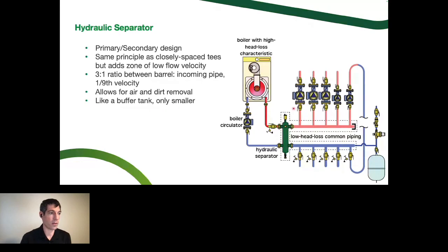We've tested this with some other devices on the market where we put a flow meter right here. You could even just look at the screens on the circulators in some cases. If you have just a boiler circulator on and you see anything other than 0 GPM on this dot right here, you're not actually separated anymore. That's the test. So if you had a flow meter here and you see some flow when none of these circulators are on, you're influencing flow across that device, and it could be that it's undersized. It could be that it's the proper device. It's just, you went with a 1-inch instead of a 2-inch or something like that. That could come up as well.